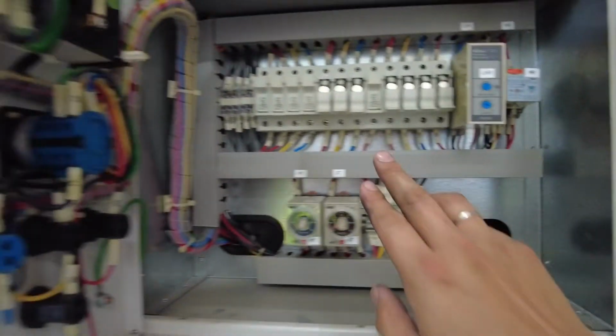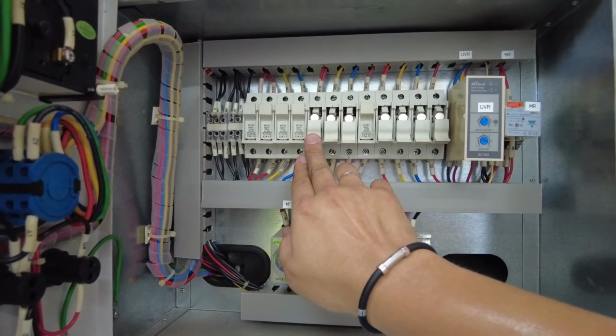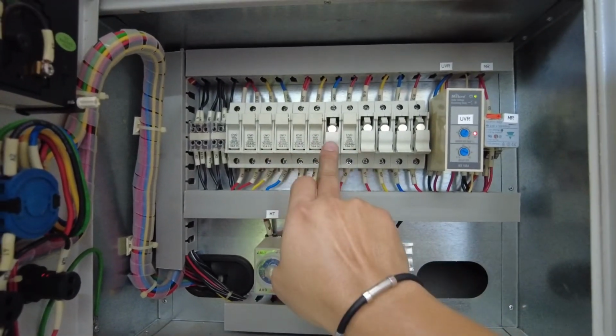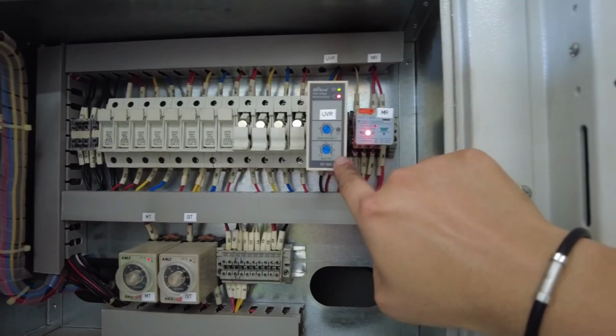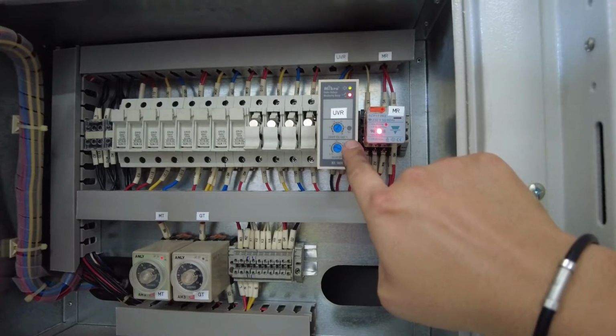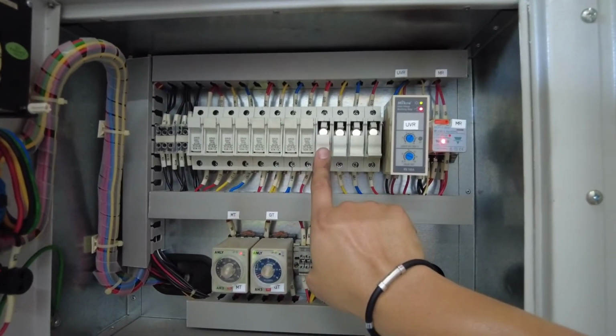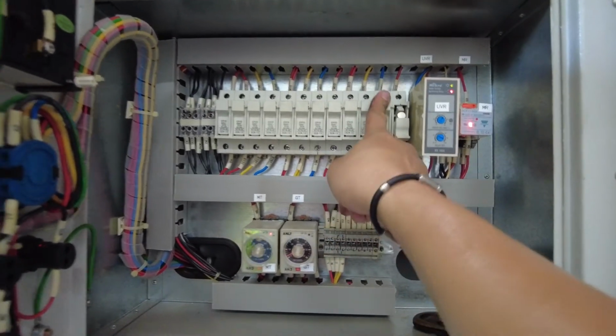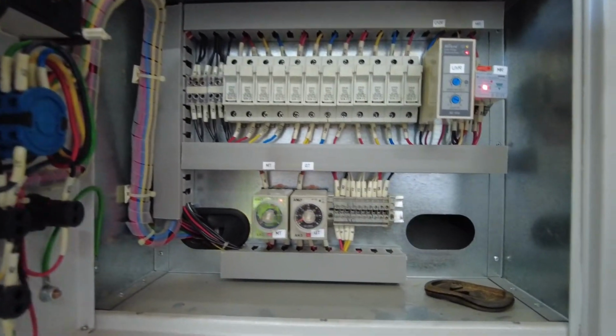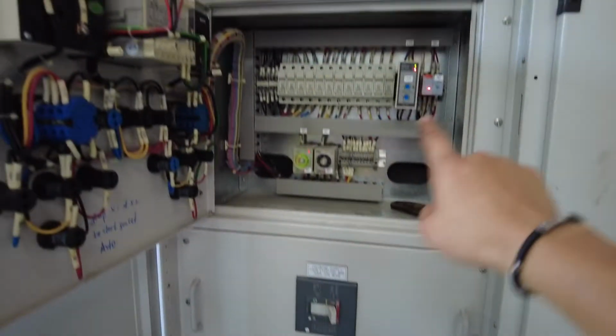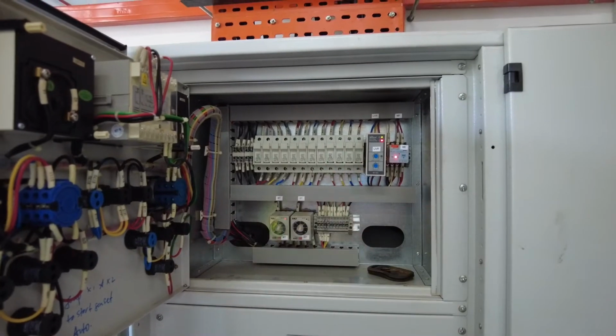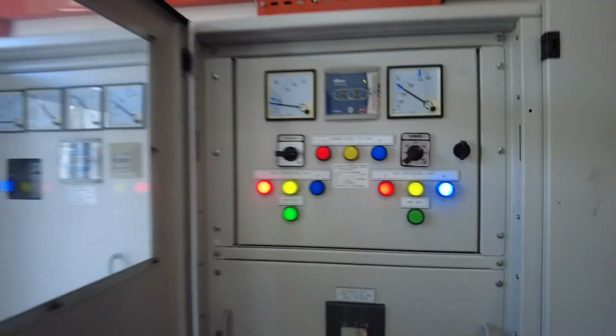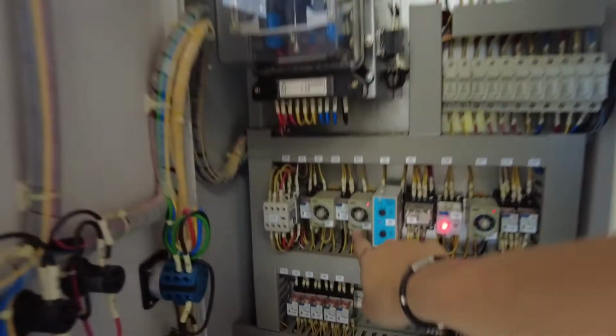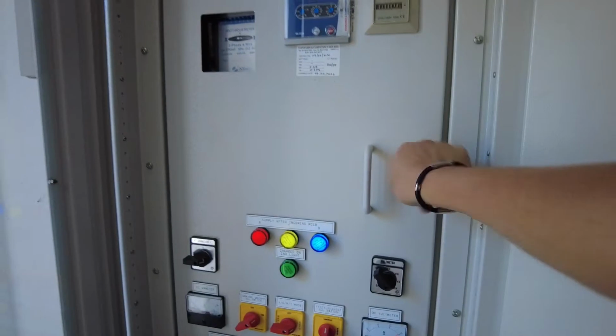Genset is running already. As you want to normalize the system, always remember, put in the control fuse for the UVR relay first and allow the UVR relay to activate. After the UVR relay is activated, only then put in the genset fuse. Otherwise, the ATS will change over and there will be power interruption. Okay, now everything is auto back. The genset will stop automatically by itself. Okay, as this one activated the shutdown timer, after 2 to 3 minutes, the genset will stop automatically and everything will go back to normal.